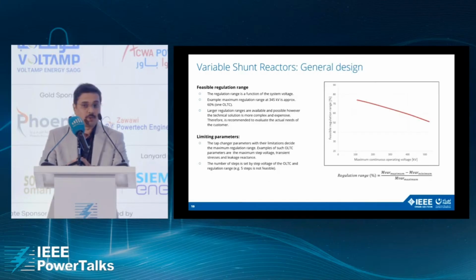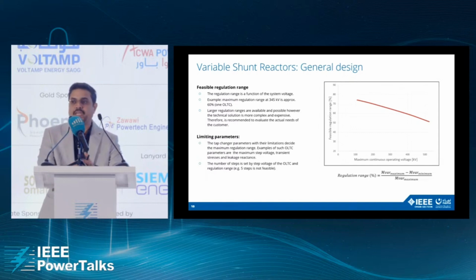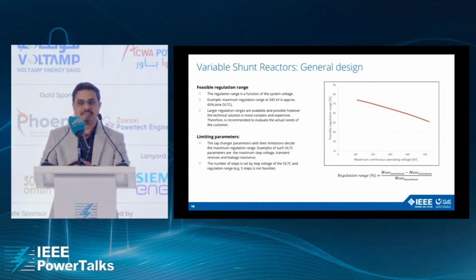Now this slide talks about the feasibility range of a shunt reactor, on how much modification, how much adjustment we can do to a shunt reactor. The graph shown here shows, across the different voltages and the total demand for reactive power, how much adjustment is possible. So you can see when you have a shunt reactor of very high voltage, coming to 550 kV, you have almost 50% variable range. And when it comes to low voltage, say for example 100 kV, you have almost 70-75% of the adjustment.